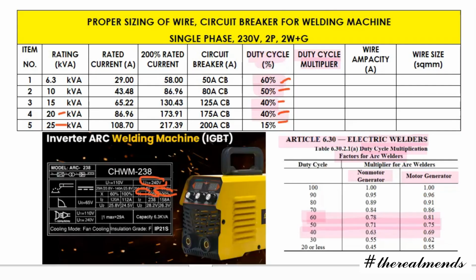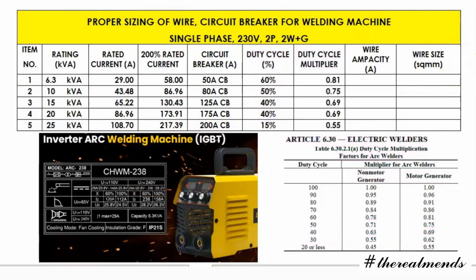Okay, the same with the 20 kVA. For 15%, actually there is no 15%, but we have 20 or less, so the multiplier is 0.55. After that, we can input these values in our duty cycle multiplier column. Okay, so these are the input values based on our table: 0.81, 0.75, 0.69, okay, 0.69, and then 0.55.